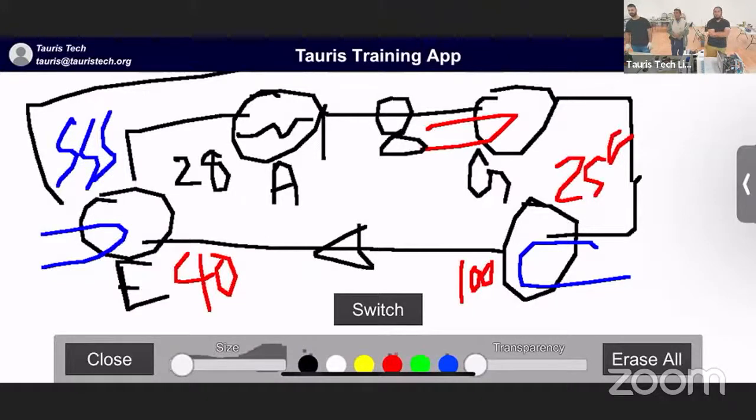So guess what? We're always sucking in what in this machine? Air. All day long. As long as this machine is running, you're sucking in air. So you have to have a purger. So a purger is essentially a vacuum pump, just constantly running, constantly sucking out air and moisture, and trying to keep the cycle going. Now, how big is that purger? Probably like that. It's a little air conditioner. A purger is just an air conditioner.